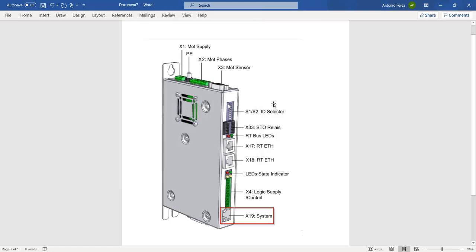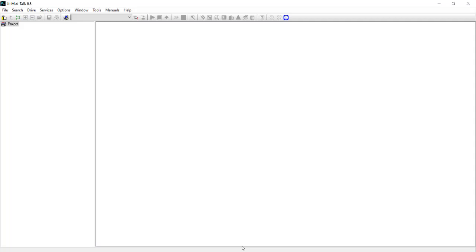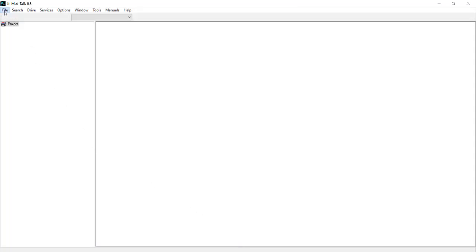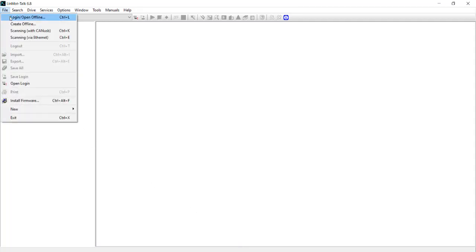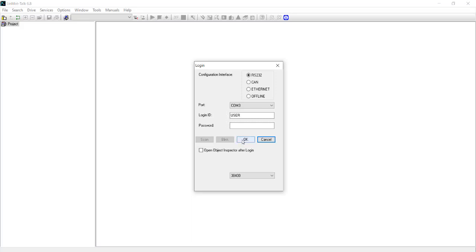Now we are ready to log into our drive. Open LinMot-Talk. Go to file, login, open offline. On the configuration interface, make sure you have RS-232 selected and the port using the correct COM that was found on the device manager. The login ID and password will be left alone. Click OK.